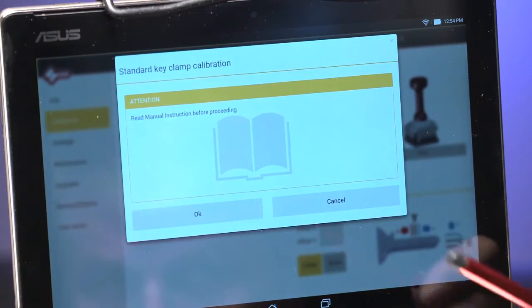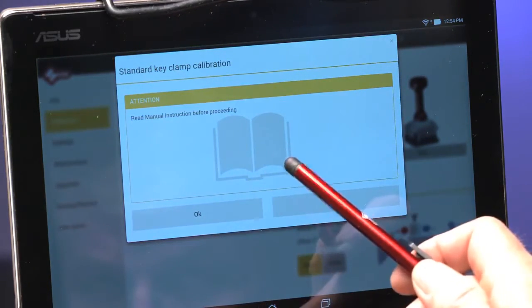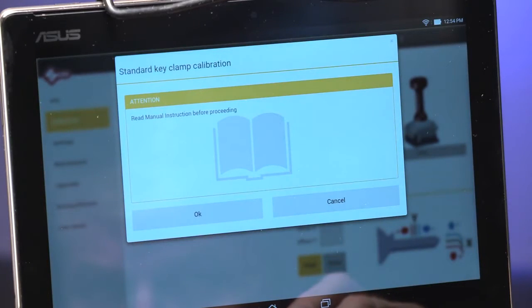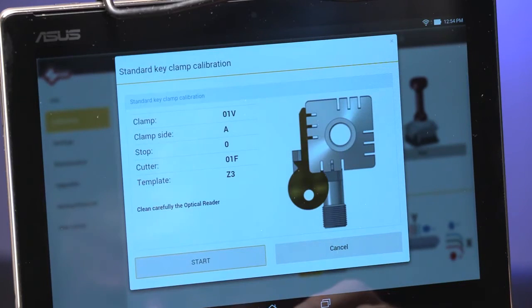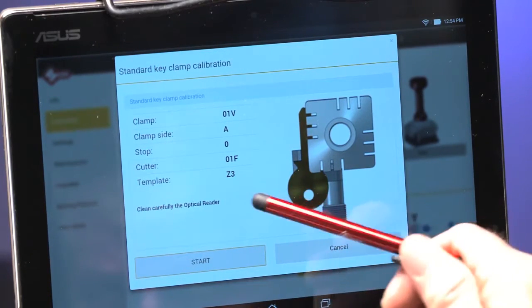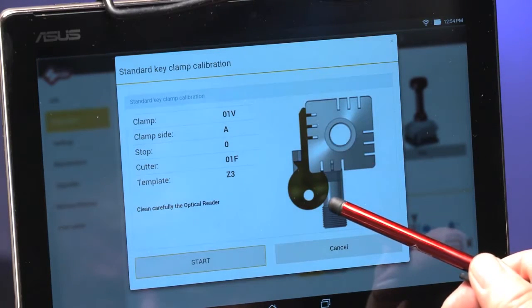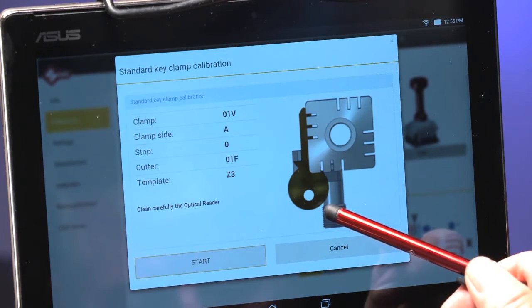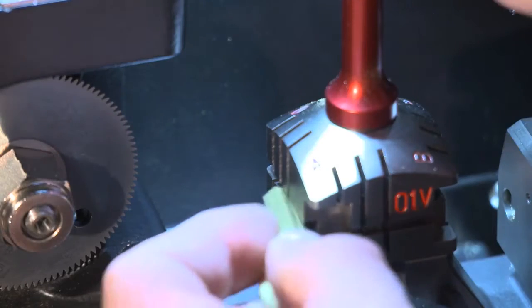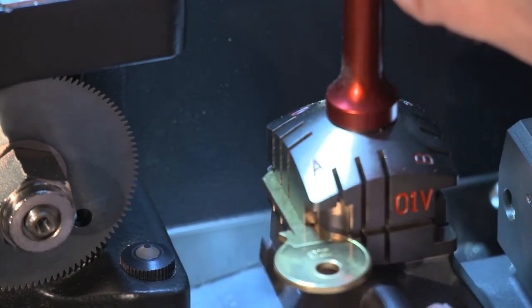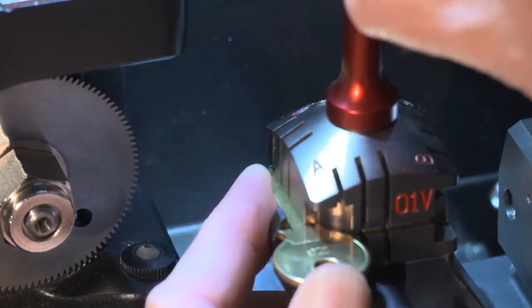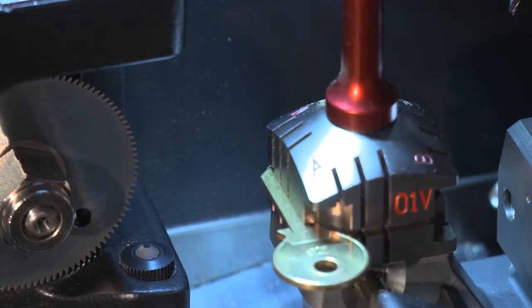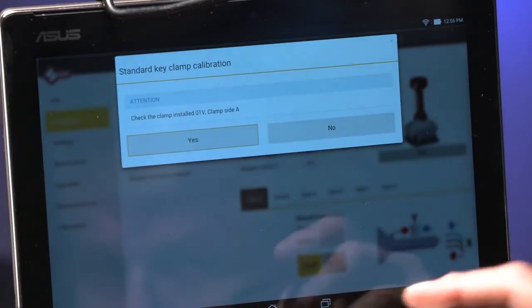Select Start to begin the calibration process. You'll receive a reminder to read the instruction manual before proceeding. Once you have reviewed the instructions, select OK. Calibration of the 01V clamp requires the use of the Z3 template key. The illustration on the tablet shows how to properly load the Z3 calibration key into clamp side A using stop 0. Load the Z3 template key as shown, and select Start to begin the process.